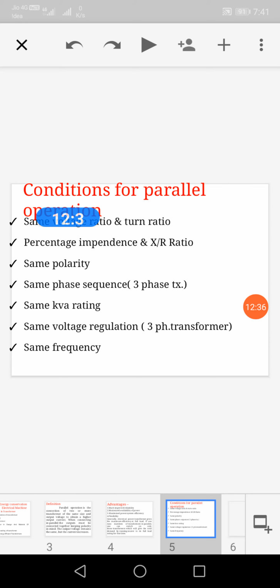Load sharing of parallel transformers depends on the kVA rating. If transformers with different kVA ratings are connected in parallel, the load division will be uneven, such that each transformer will carry load in proportion to its rating. The frequency, India's frequency being 50 Hz, of both transformers should be the same, and this is the condition for the parallel operation of transformers.